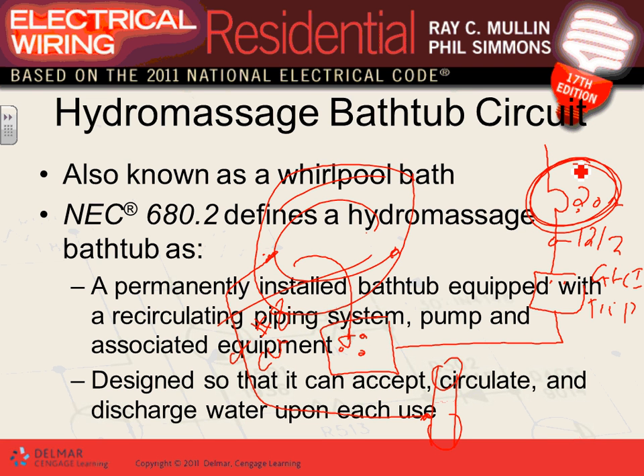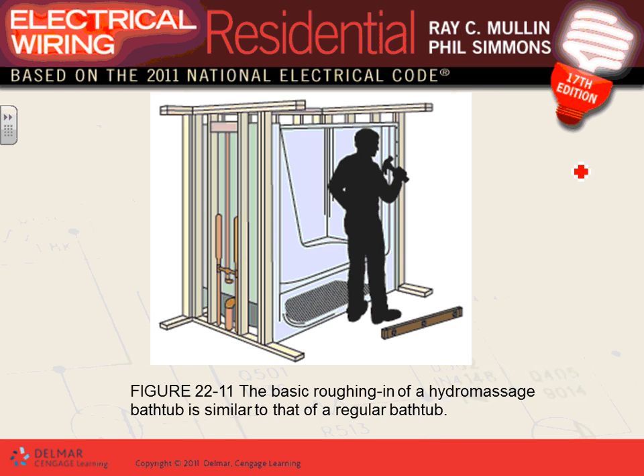So that's my hydromassage bathtub. It is designed so that it can accept, circulate, and discharge water upon each use. Bring water, circulate the water, and discharge it every time you jump into that bathtub. How do you wire it? 20 amp circuit, like I told you. Don't forget about the bonding with number 8. Any comments, any questions about the hydromassage bathtub? We don't have it in our system here. Okay, so there you go.